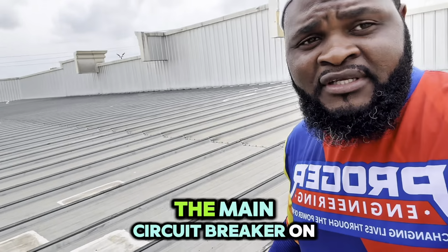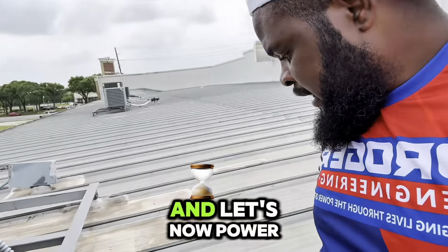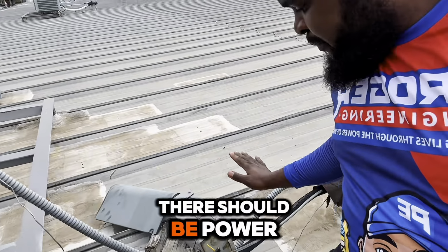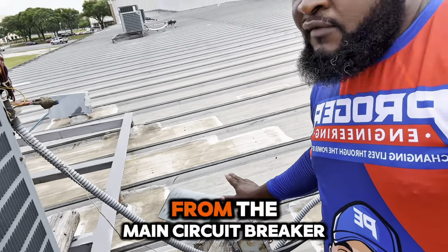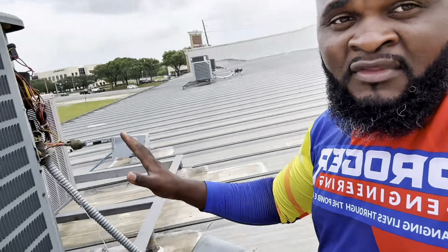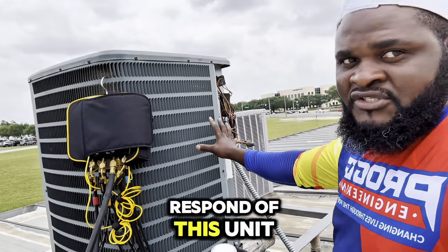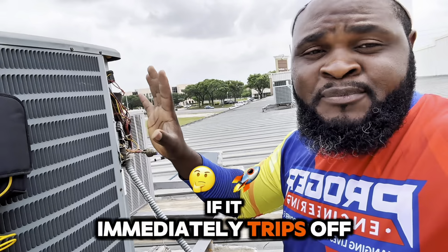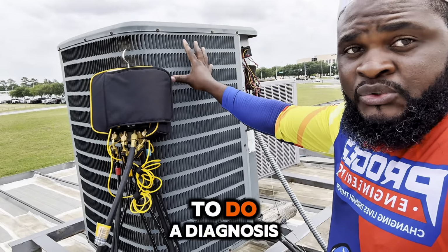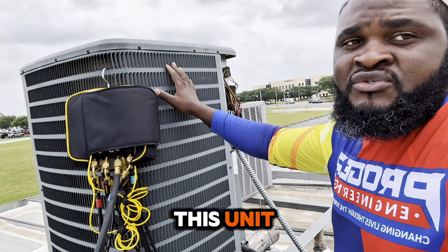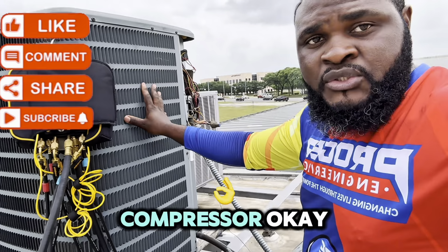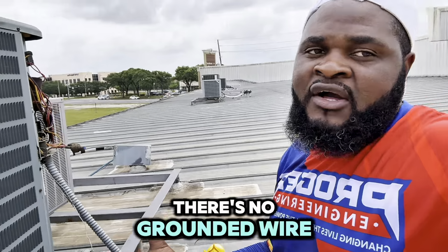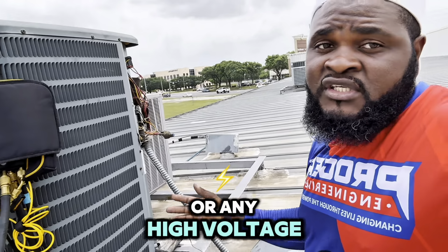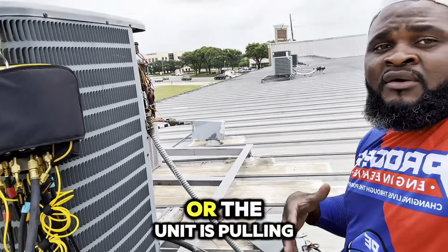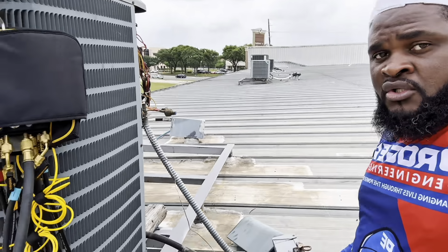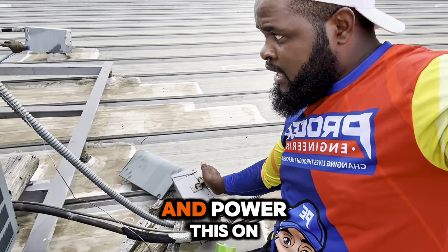We have turned the main circuit breaker on, and let's now power this unit. So there should be power getting into this disconnect now from the main circuit breaker. So let's power on and listen to the response of this unit. If it immediately trips off, then we'll go ahead and diagnose the main components of this unit. That's the motor and the compressor, okay? To make sure that there's no grounded wire or any high voltage wire that is grounded, or something is happening, or the unit is pulling higher amperage. So let's go ahead and power this on.